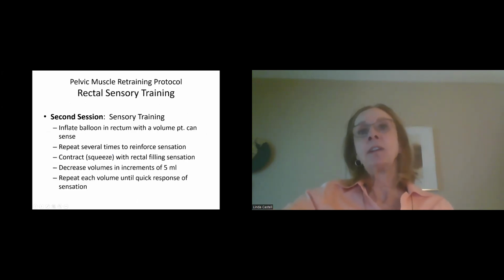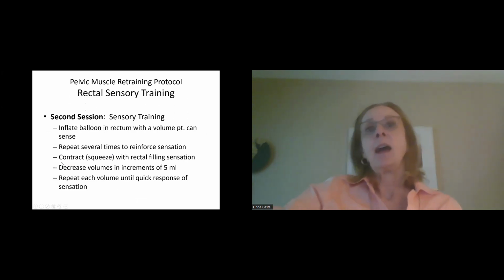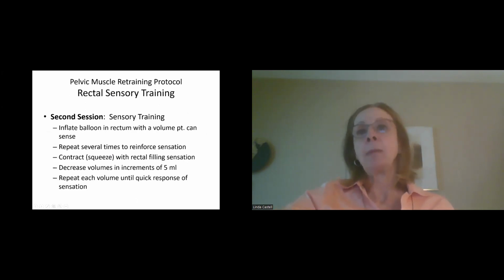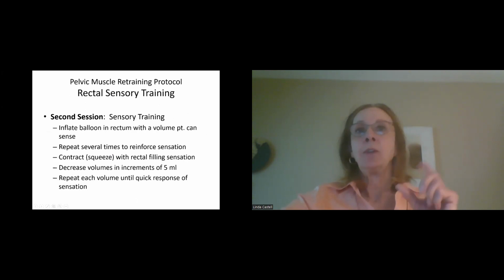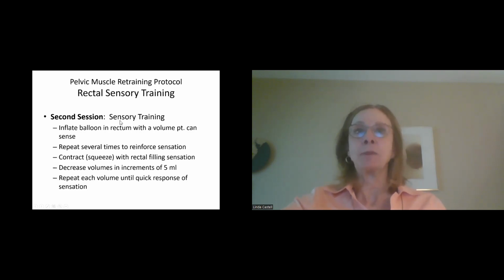On their second session, we're going to use our manometry catheter because it has a rectal stimulation balloon on it. If you're currently doing manometry, your catheter may be the high resolution one where you have lots and lots of sensors. That's great. If you're using a catheter with 4 sensors, you're going to turn off 3 of those sensors and only look at 1. You don't want your patients to have so many sensors to look at. So we turn on the rectal stimulation balloon, and we keep the posterior channel on and turn off left, anterior, and right, if you have that 4-channel disposable catheter.